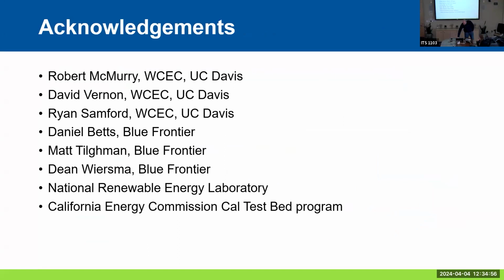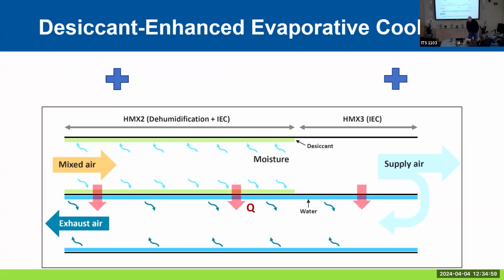It is the Cal Test Bed Program. So what is this? It's a combination of two technologies: one is indirect evaporative cooling, and the other is desiccant dehumidification. A lot of people are familiar with direct evaporative cooling - like a swamp cooler. You run hot, dry air across a wet medium, the moisture evaporates, and you have cool, moist air. That can be effective in dry climates, but it can also be a little too damp for people.